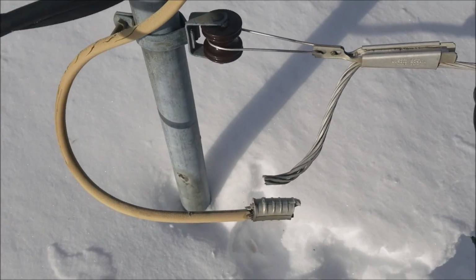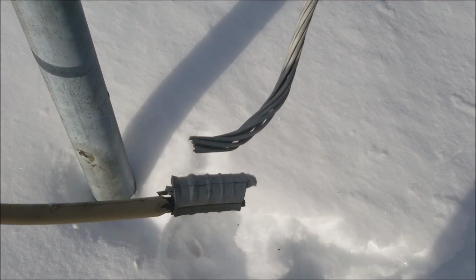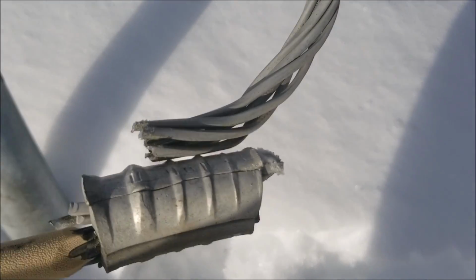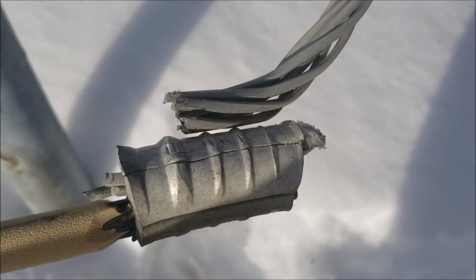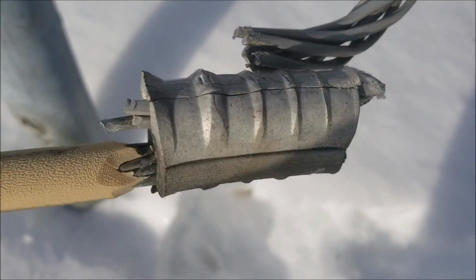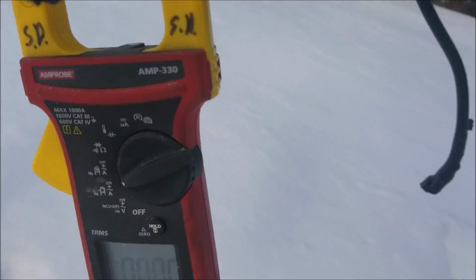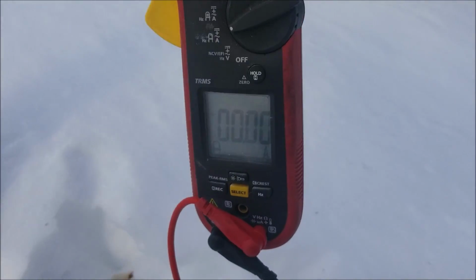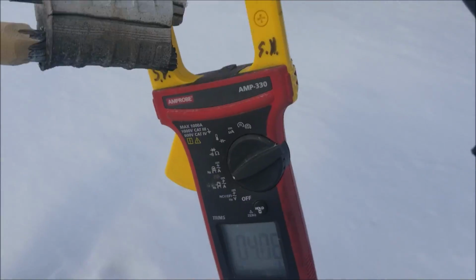In fact, I was lucky enough to capture a perfect example of fault current through a neutral wire only a few days after this accident. While working on a customer's service, we found there to be an unusual amount of current flow through a de-energized triplex loop which had just been cut from the customer's mast.